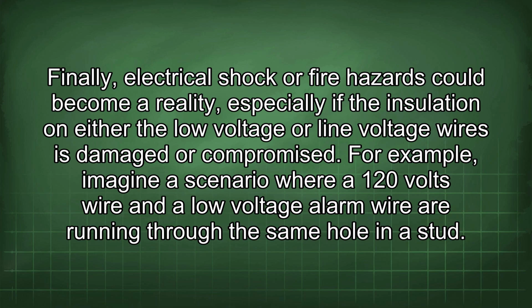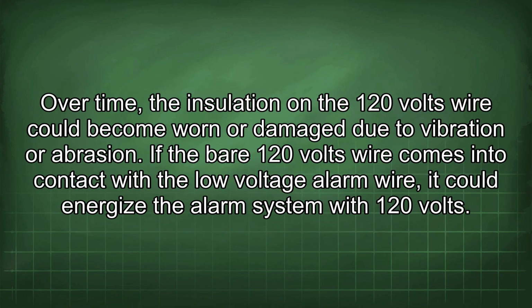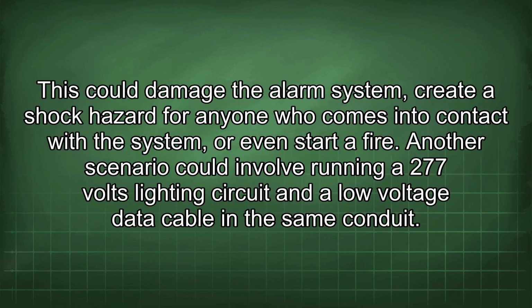For example, imagine a scenario where a 120 volt wire and a low voltage alarm wire are running through the same hole in a stud. Over time, the insulation on the 120 volt wire could become worn or damaged due to vibration or abrasion. If the bare 120 volt wire comes into contact with the low voltage alarm wire, it could energize the alarm system with 120 volts. This could damage the alarm system, create a shock hazard for anyone who comes into contact with the system, or even start a fire.